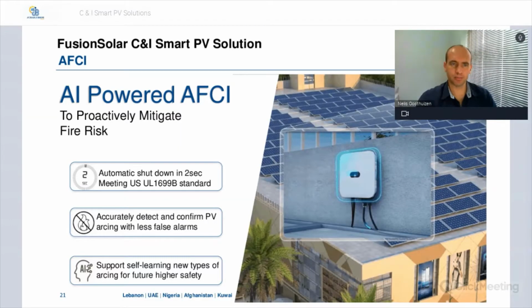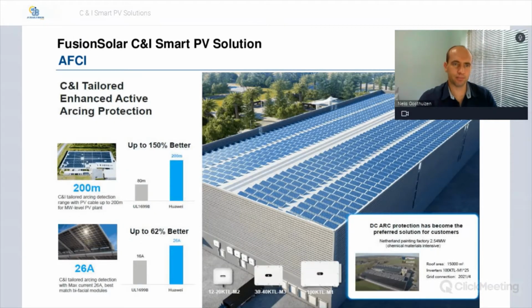On the AFCI on the Huawei inverters, there's automatic shutdown in 2 seconds, meeting the UL 1699B standard. It can accurately detect and confirm PV arcing with fewer false alarms. And because the Huawei inverters have artificial intelligence powered AFCI, it supports self-learning new types of arcing for future higher safety.